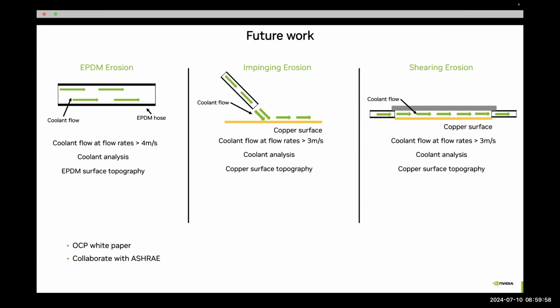I can say that one. I think it would apply to two phase as well. I don't think in ASHRAE we define it by cooling technology. It's just the idea of the fluid interacting with the piping. So obviously one type of mechanism would be with water, and there may be an erosion corrosion mechanism, but you would still have erosion even with the refrigerant. But the only thing is that in two phase, you have very low velocities, so maybe that's helpful, right?